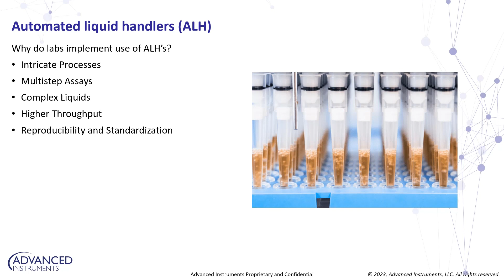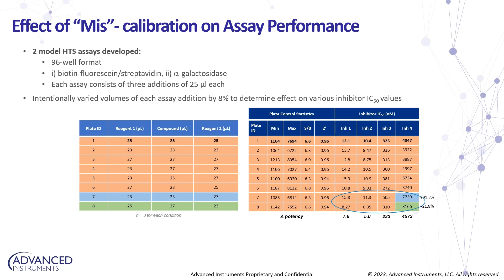Now, we wanted to take a look at what's really the impact of some of these small changes. What's really the impact of something like 2 microliters? We took a model high throughput screening assay with key components, reagent 1 and reagent 2 compounds, that were supposed to be delivered at 25 microliters. We intentionally varied those volumes by plus or minus 2 microliters to measure the impact of the potency, or the IC50, at the conclusion of the test. And on the bottom right-hand side of the screen, the measured IC50 had a very widespread min to max just by adjusting those reagent volumes by 2 microliters.